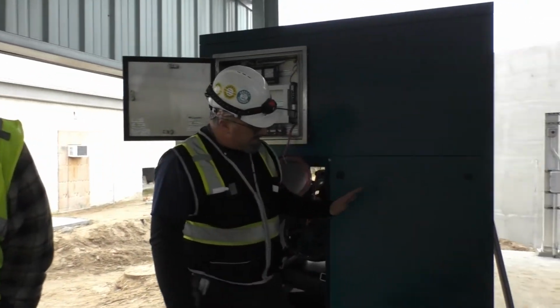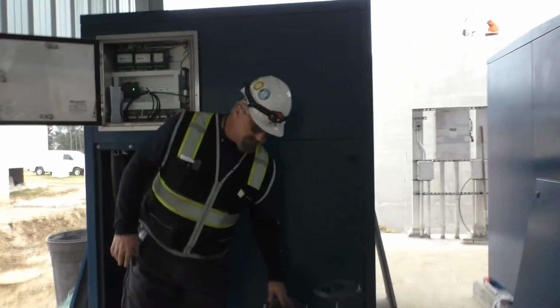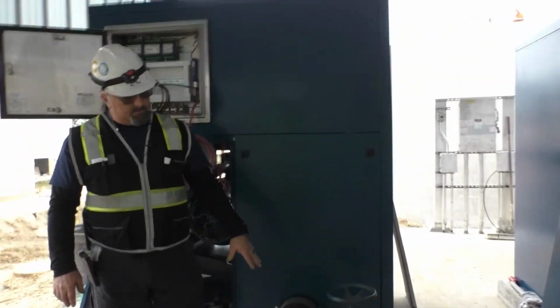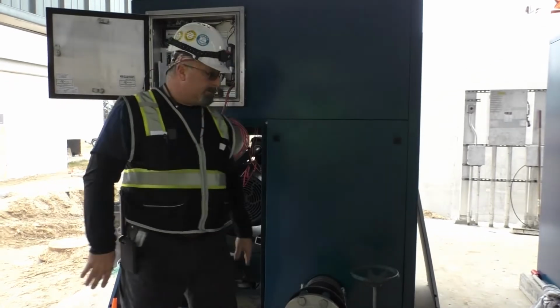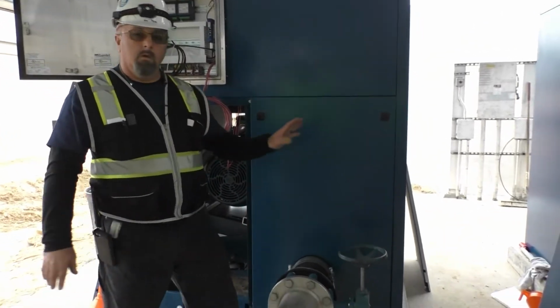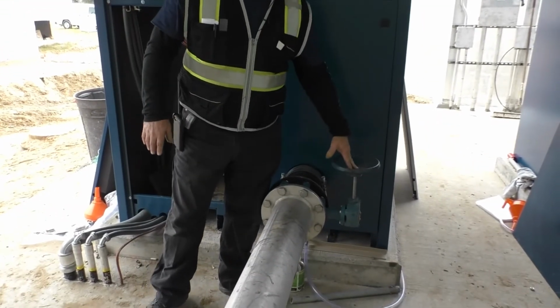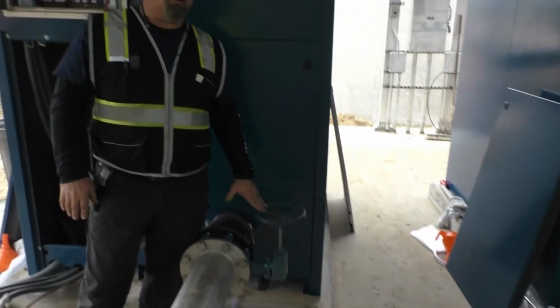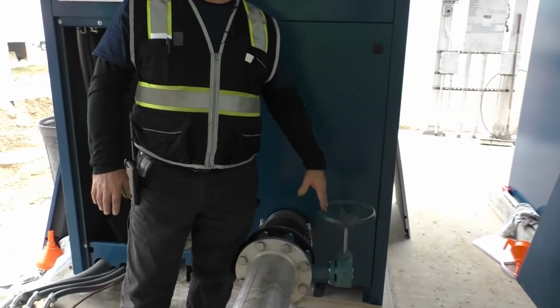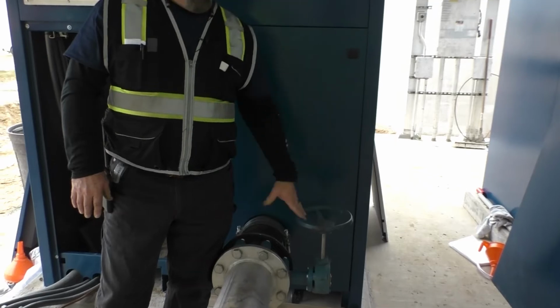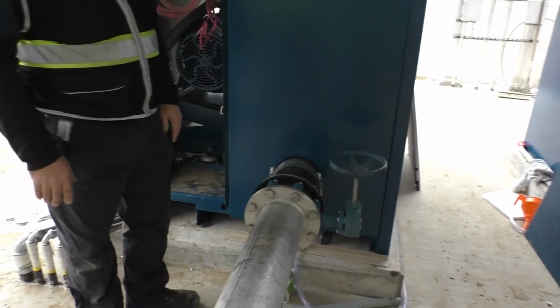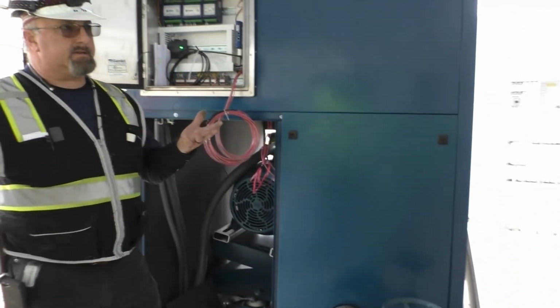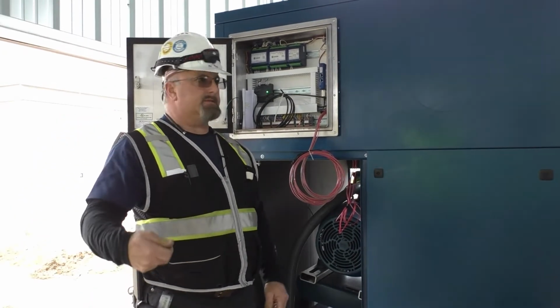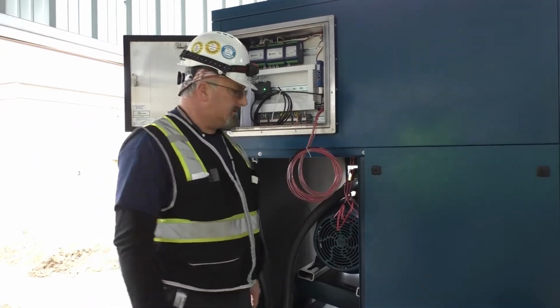All right, back here on the back of the unit, you have your flex connection that connects you up to the valve and your piping going out to the system. You always want to make sure that if this blower can go into automatic operation, all valving that's not automatic is open. Or, for your aeration, if there's a particular place that you set it at, you want to make sure that it's set.